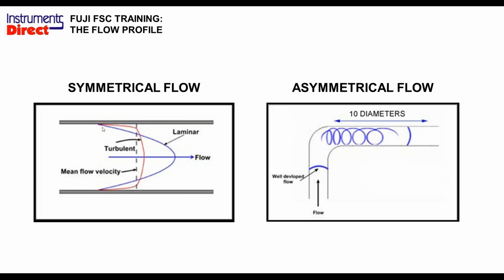So fast or slow doesn't make a difference, but if you have enough straight run of pipe, you'll have this symmetrical flow profile. This normally occurs 10 pipe diameters downstream from an elbow, put your sensor here, and another 5 pipe diameters before the next elbow. So that's your generic default for flow rates that are around 10 feet per second. Most pumped flows are between 7 and 10 feet per second, so that's pretty much your go-to straight run of pipe for optimum performance of your flow meter.